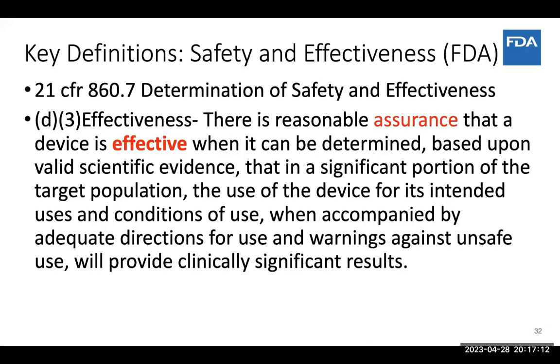In Europe it's different. The European Union gives CE approval, which is equivalent to FDA approval, but they're more concerned with safety. Because of this, many US companies first go to Europe to get CE approval—it creates cash flow and they gain experience. If there are bugs in the system, they fix them and collect a lot of data before coming to get FDA approval. For example, the hematoma product I showed you from our company had CE approval in Europe for several years before we were able to get FDA approval.